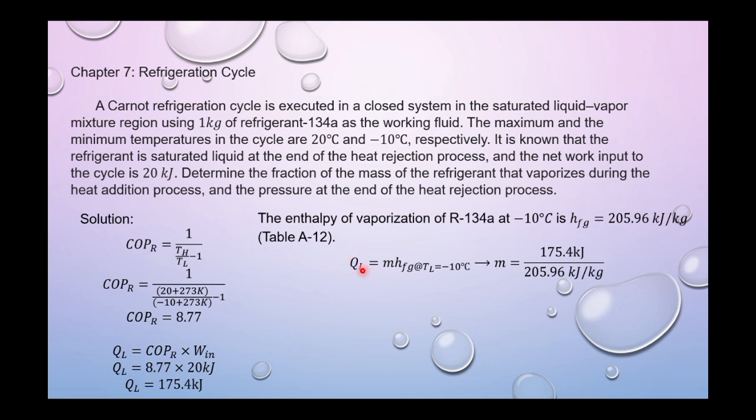To find the mass, QL equals mass times hfg at TL = -10°C. Mass equals 175.4 kJ divided by 205.96 kJ/kg, which is the hfg at -10°C. Our mass equals 0.852 kg.